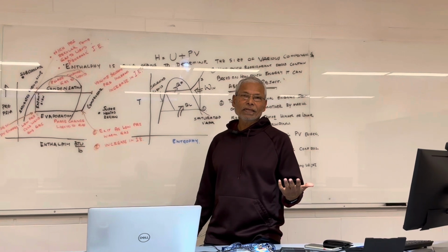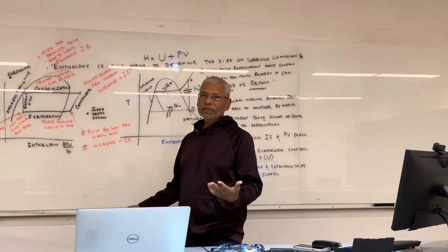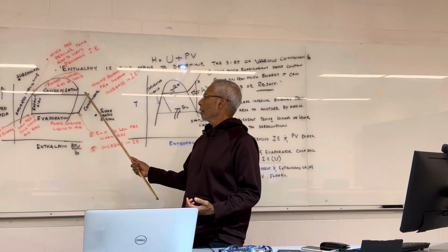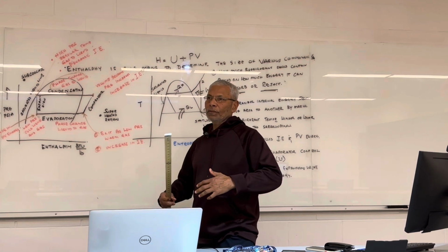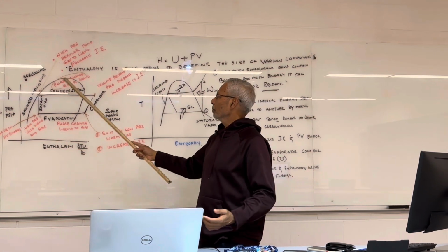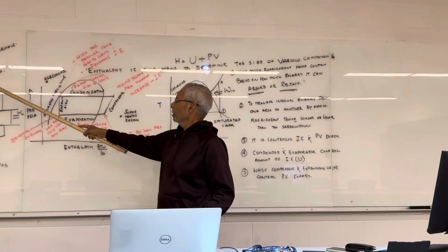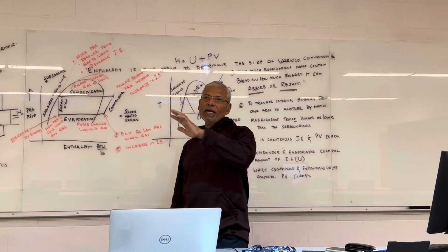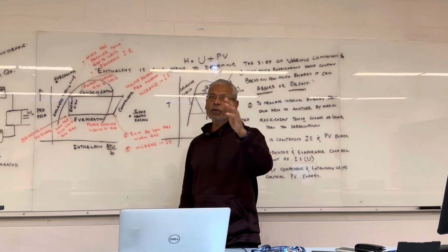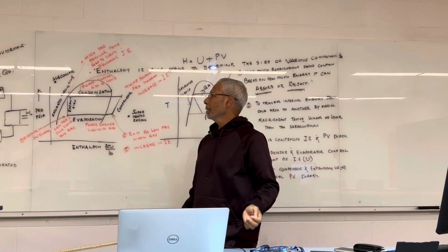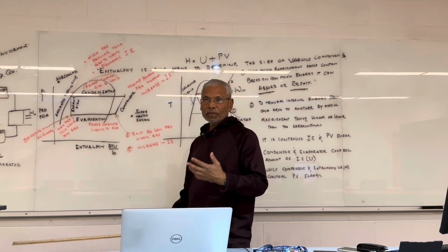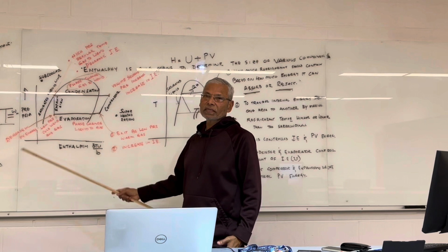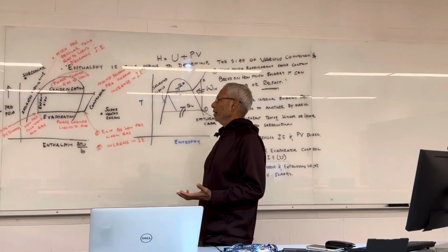The condenser is nothing but a heat exchanger. The evaporator is also another heat exchanger. So what you're doing is the high temperature, high pressure gas that is going through, you're rejecting the heat into the atmosphere. So that's why you see that heat rejection taking place here. While you're doing that, from high pressure, high temperature, running through the condenser coils, and you're rejecting the heat, there is a phase change taking place, because remember, it's in a vapor state, and it is turning into liquid. By the time it comes out of the condenser, it's already a saturated liquid, right?